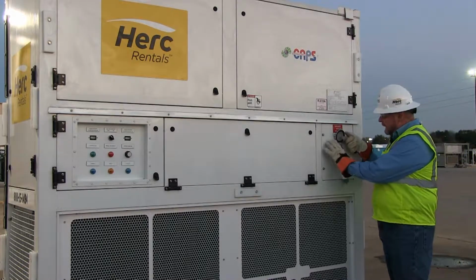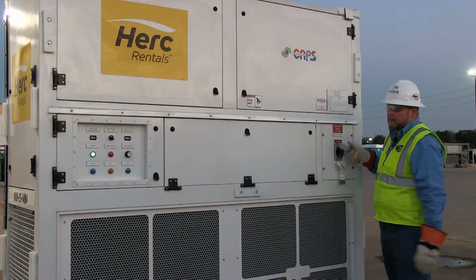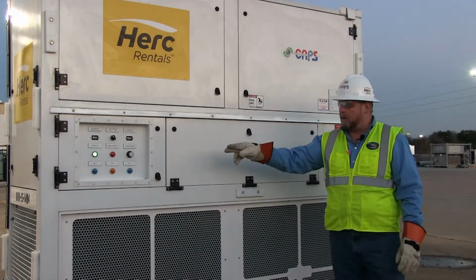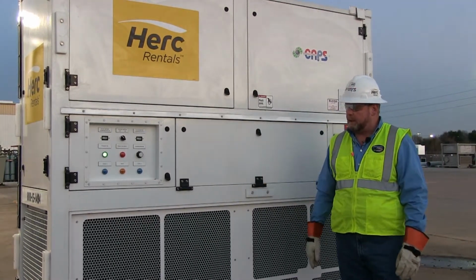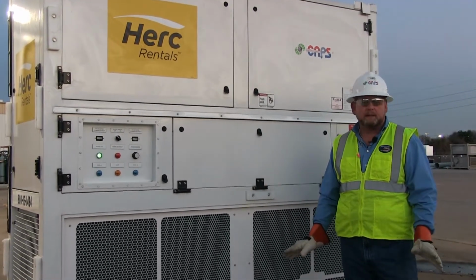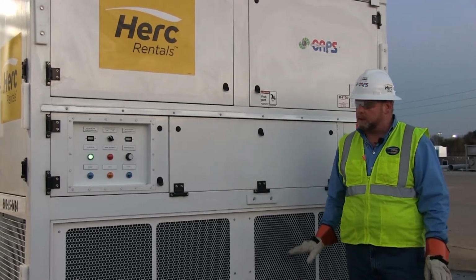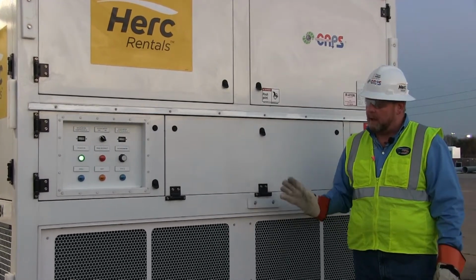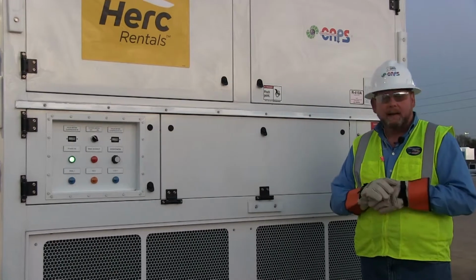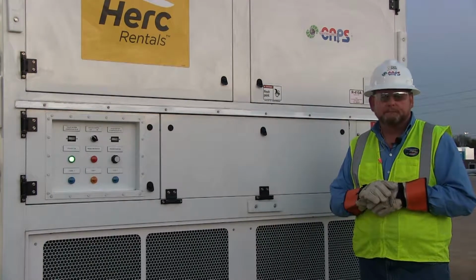We're going to re-energize the main circuit breaker. Now you'll notice this time we have a power light and our phase incorrect light is now off. The machine is now warming up the compressors and the compressor crankcases. Now we can go around on the other side and have a look at how to connect to the tent.